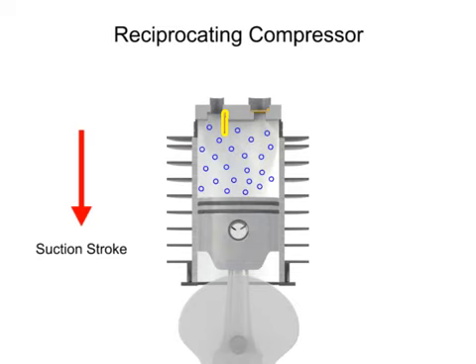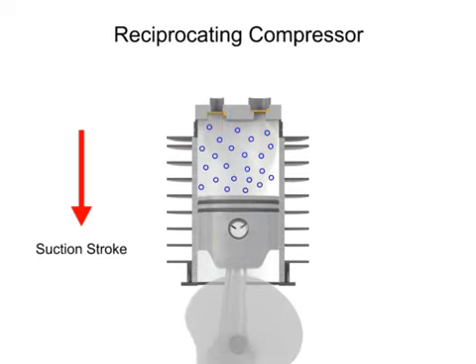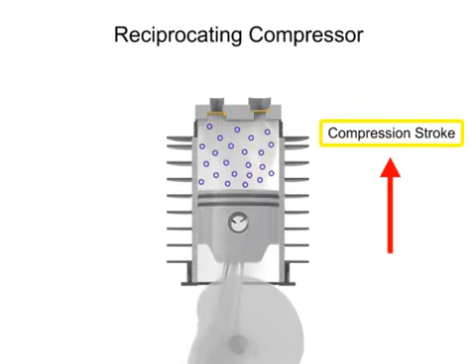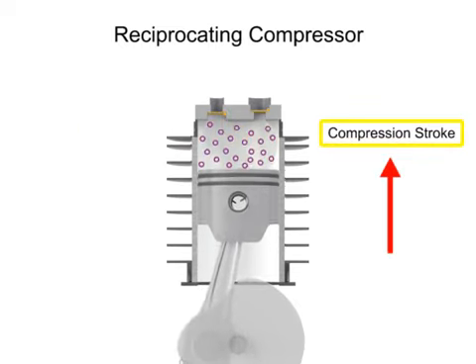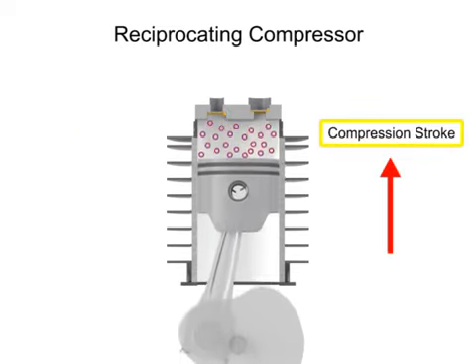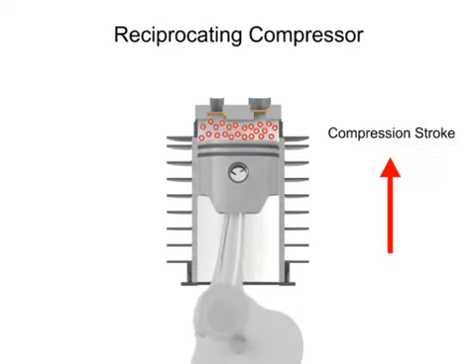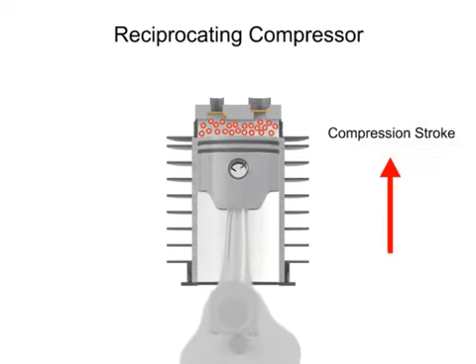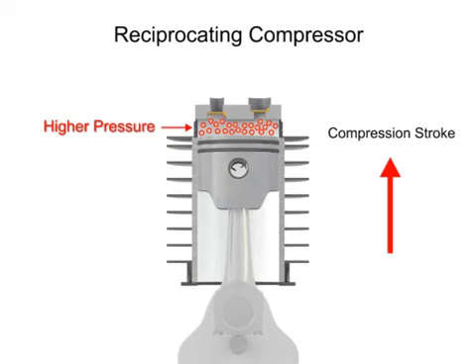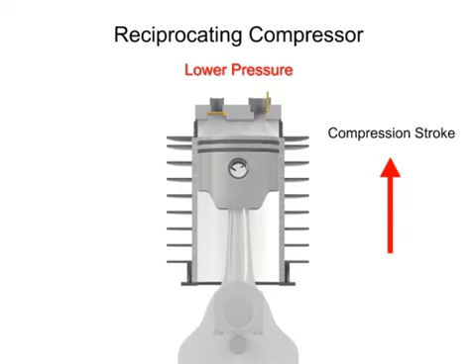As the piston begins its upward compression stroke, the volume within the cylinder decreases. The decrease in volume causes the pressure within the cylinder to increase. The increase in pressure opens the outlet valve and compressed air discharges from the cylinder.